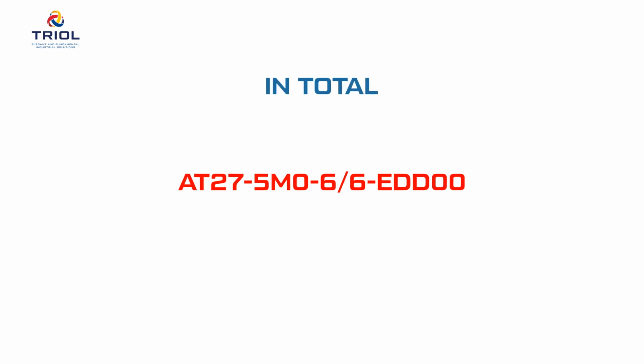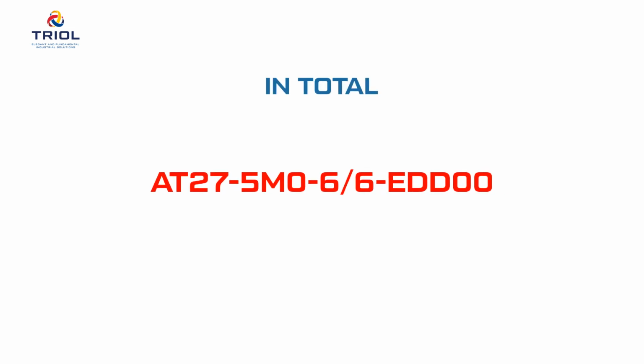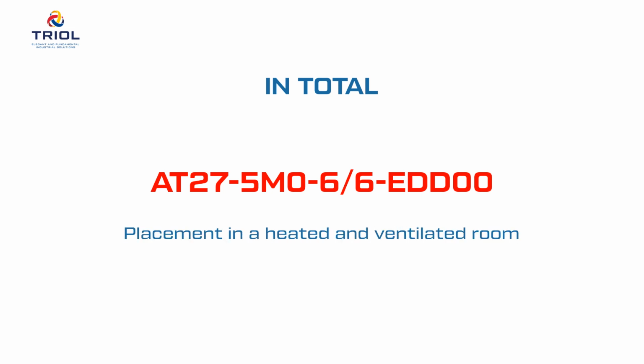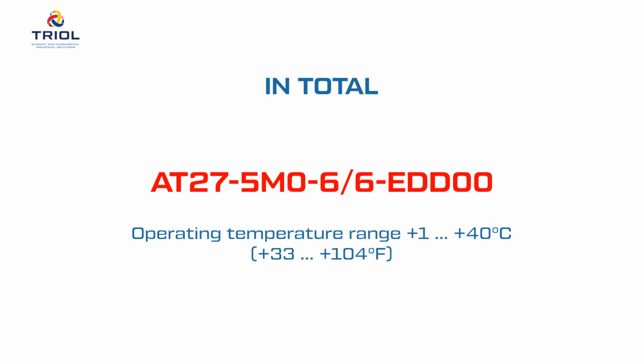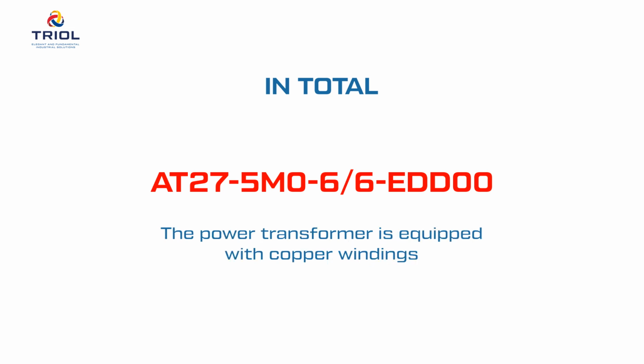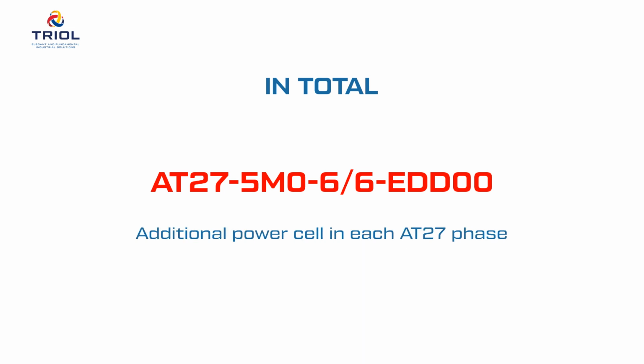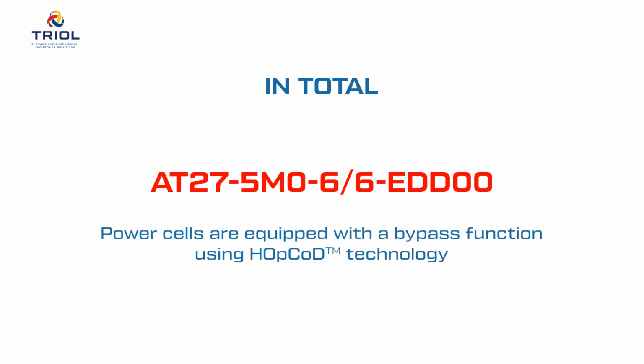In total, we get the name AT27 VFD, providing the following technical capabilities: frequency drive with an operating voltage of 6,000 volts and an output power of 5,000 kilowatts. Designed for placement in a heated and ventilated room, it has an IP31 enclosure, operating temperature range +1 to +40 degrees Celsius. The power transformer is equipped with copper windings. The power section contains an additional power cell in each AT27 phase. Power cells are equipped with a bypass function using Hopcod trademark technology.